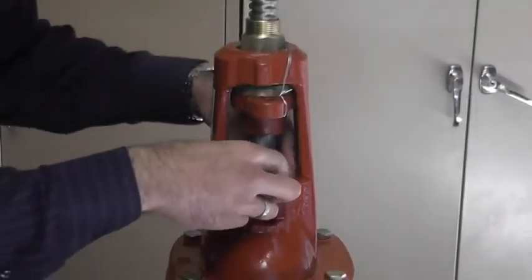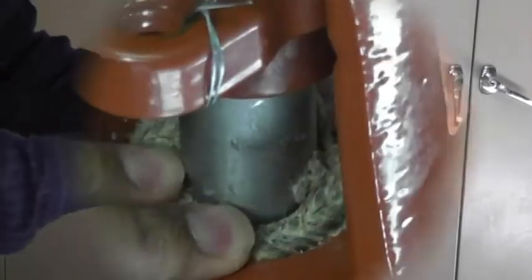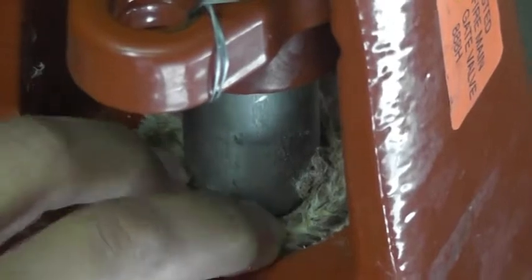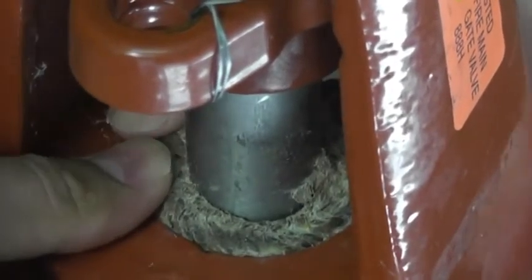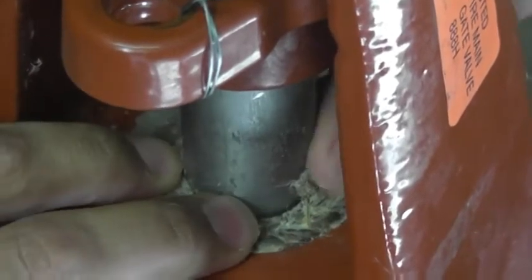Insert the first piece of packing into the valve body by wrapping it around the stem and pushing it down into the valve body. Once the first piece of packing is in, repeat with the remaining pieces of packing. Be sure to stagger the opening of each packing so they are not on top of each other. Do not worry about compacting the packing as this will be done with the packing gland later.